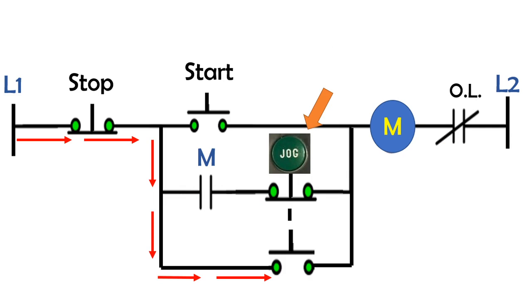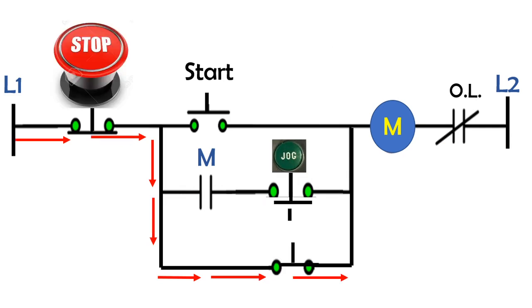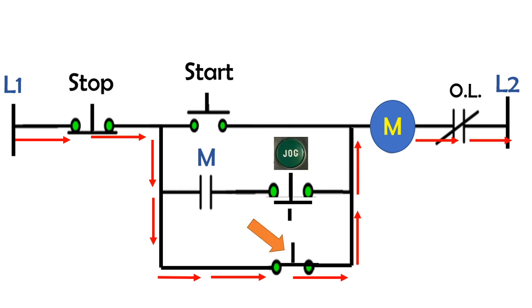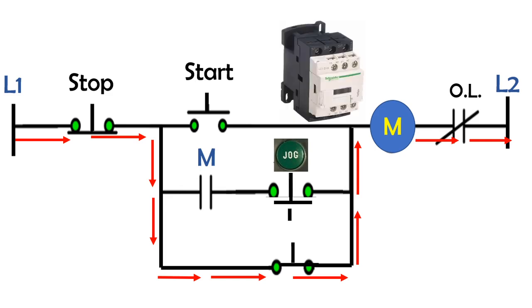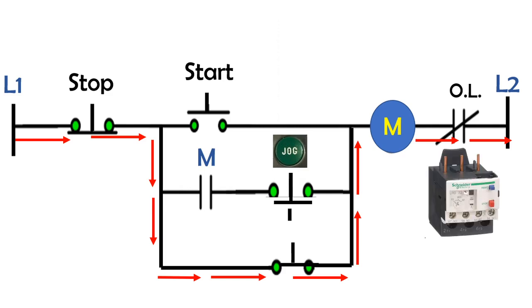When you press the jog pushbutton, current will flow from line one through the stop pushbutton, through the normally open pushbutton that is held closed momentarily, through the magnetic contactor and overload relay, then back to line two.